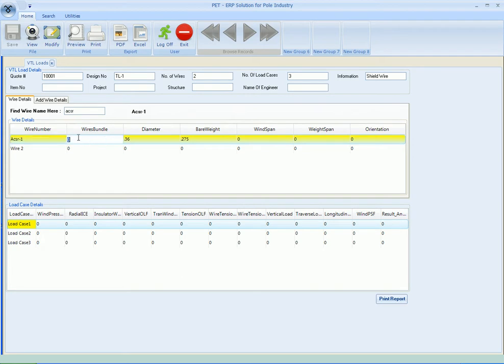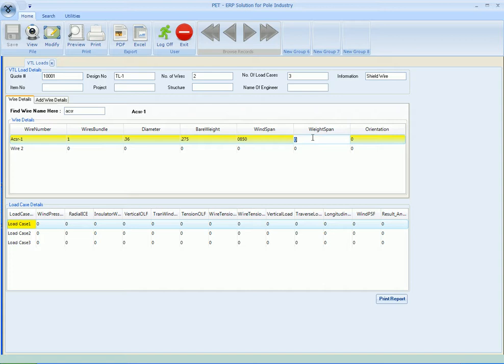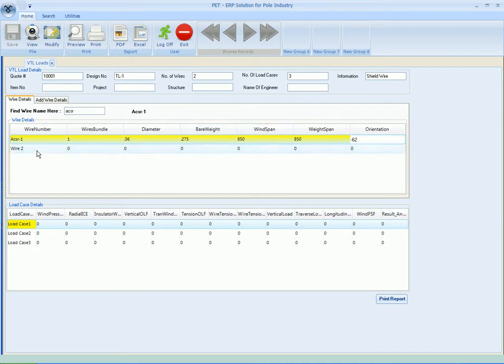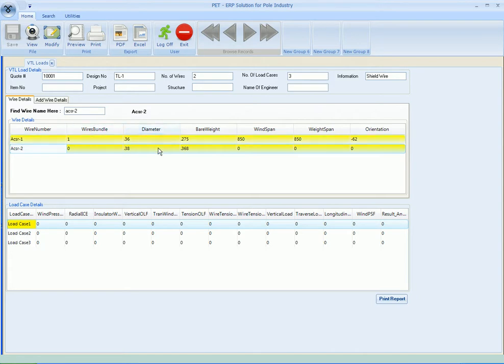Now come to the wire bundle - say one. Wind span let's say 850, weight span let's say 850. The wire orientation let's say minus 62. And the same way for the second wire we will again enter here name - let's say it's ACSR 2. Press the tab - you will get the bare diameter and the bare weight.